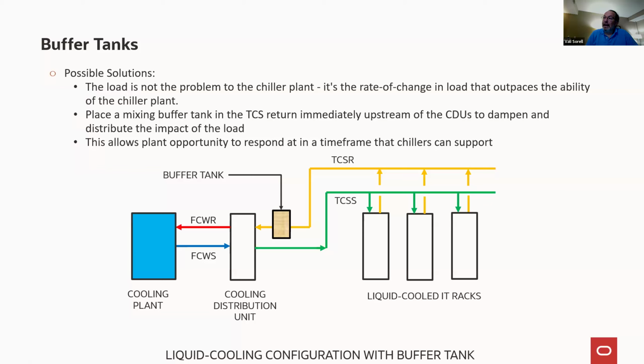It doesn't have to be a stratified tank. It's a mixing tank. For those who really deal with mechanical systems, you often hear of thermal storage tanks. Some people call them buffer tanks, but the difference is a thermal storage tank is put right here in the facility cooling water supply side, because if you lose power and the chillers drop out for 2 or 3 minutes or 5 minutes, you still have a reservoir of cold water, so you can keep the IT racks happily cooled for the duration of that outage.